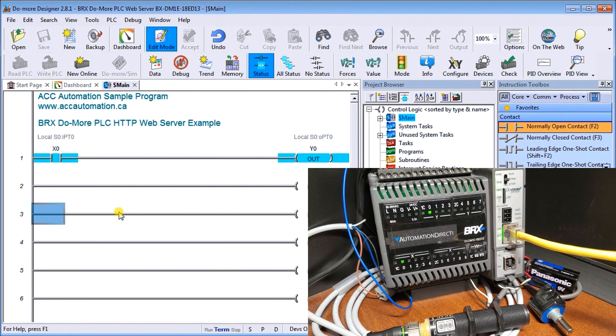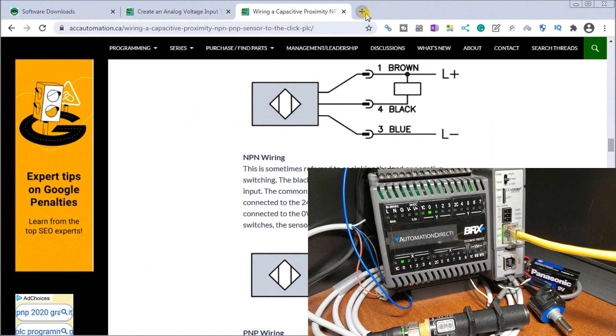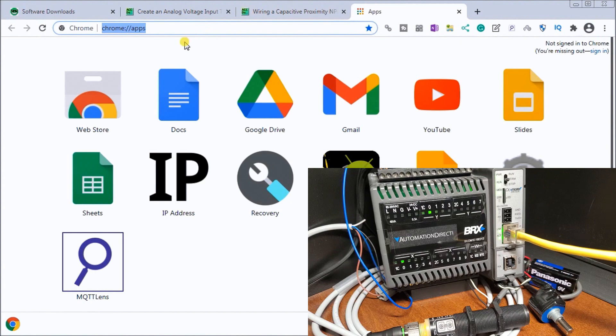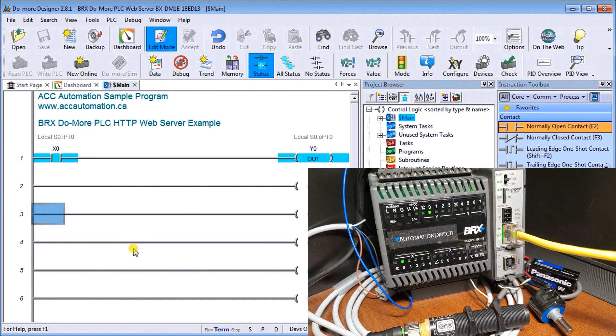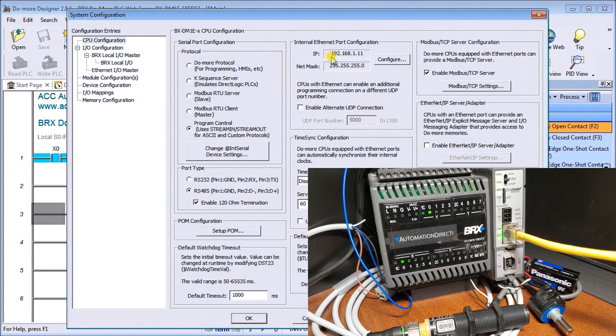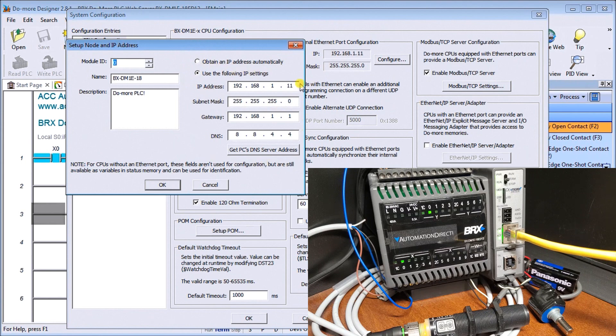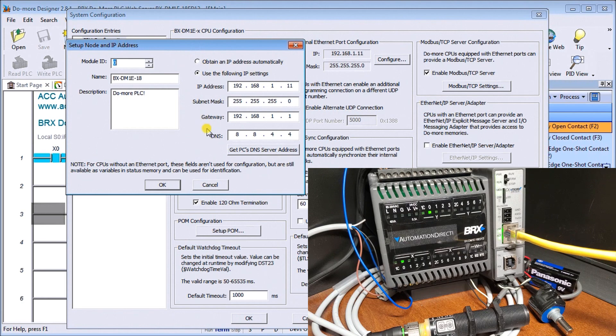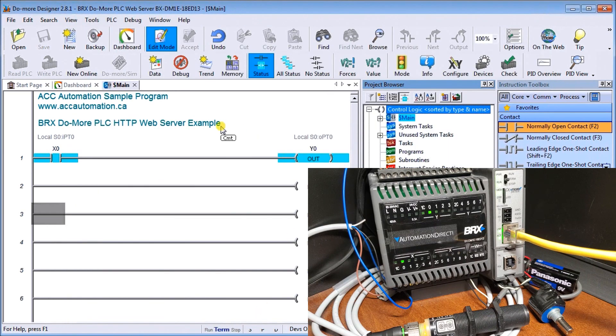Next on our testing we have to call up our website. Through the system configuration, our IP server of this BRX unit or BRX Do More PLC is 192.168.1.11. When we configure it we have to make sure that we actually use a static IP address. This ensures that we know exactly what the value is to put on the IP address in order to reach that website.